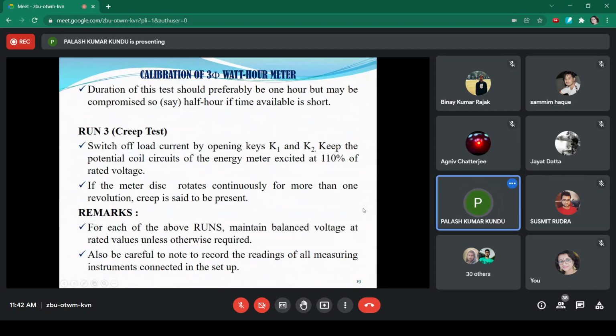What are the conditions? Essential conditions must be followed. First of all, the three-phase supply voltage should be balanced, otherwise there will be error in measurement. The reading should be recorded for all measurements connected to the setup. That is, the ammeter reading must be the same, so that there are no variations of the load current flowing through the current coil of the test energy meter as well as the wattmeter. So these are the mandatory conditions that must be followed carefully for carrying out the experiment.